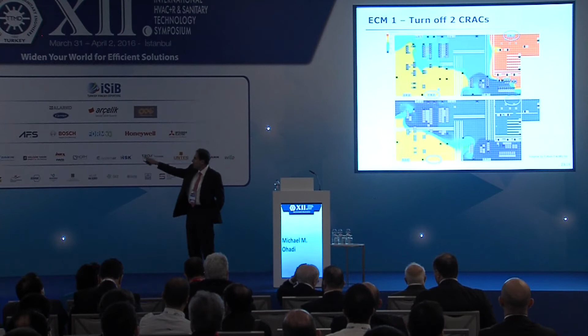If you look at this graph, we found that turning off two CRACs actually improves data center operation. We had too many CRACs in this room, and the CFD model shows we could turn off two of them. Red is not good, blue is good, as shown in the color coding. We identified that three CRACs could be turned off, but facilities management and IT wanted to keep one working for redundancy in case of failure, and we agreed that was fine—two for sure.